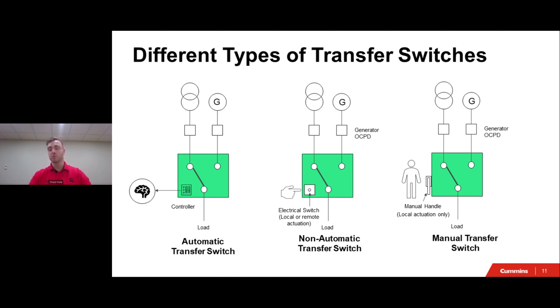And then once power is restored or you are able to switch back to the utility, the automatic transfer switch will sense that, and then it will transfer from the emergency power source back to the normal power source. And then it will send a signal to the generator to shut down.